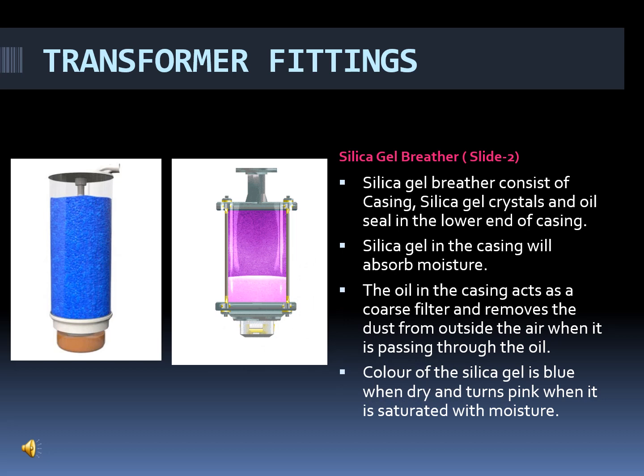By continuing into the topic of Silica Gel Breather, now understand the parts of the Silica Gel Breather. The Silica Gel Breather consists of 3 parts. One is the casing, second is the silica gel crystals and third one is the oil which is at the lower end of the casing. The silica gel in the casing will absorb the moisture. The function of each one: the silica gel in the casing will absorb the moisture and the oil in the casing acts as a coarse filter and removes the dust from the outside when it is passing through the oil. And let's see the colors of the silica gel.